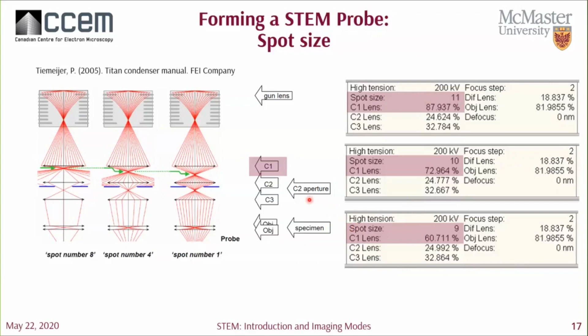So this is just an example from the microscope. We have a spot size of 11, 10, and 9. As you can see, as we increase the spot size, we're increasing the strength of our C1 lens. Normally, increasing the spot size by 1 tends to decrease the beam current by half. So in using a higher spot size to form a better probe, this gives us a dimmer beam, or a less bright beam. So it's good that you have a bright source, to increase the brightness of your probe, allowing you to get a good signal on your detector.